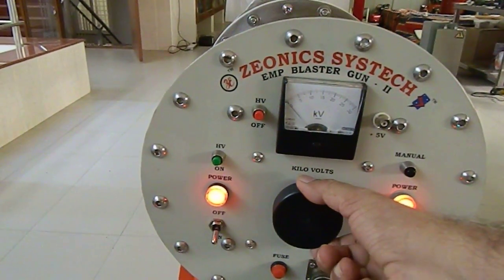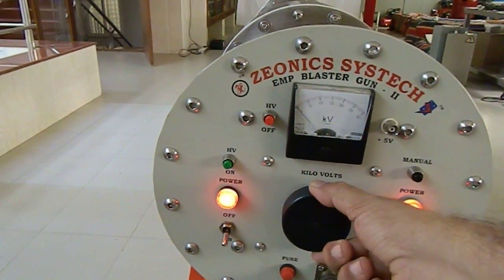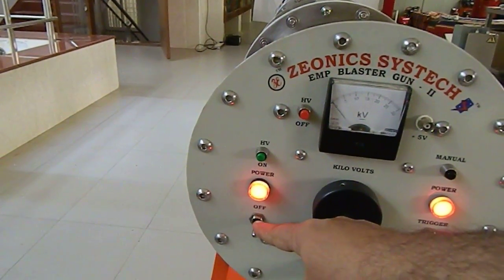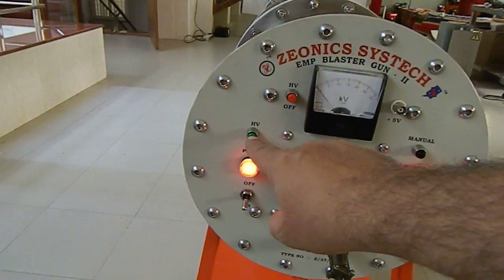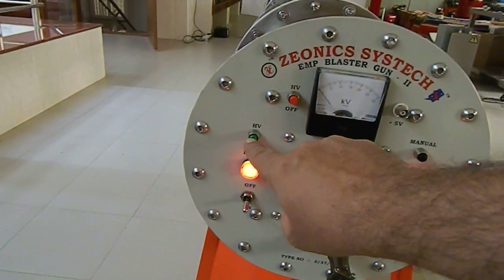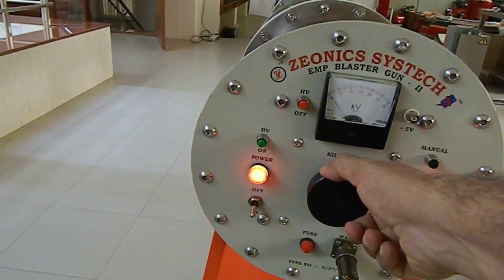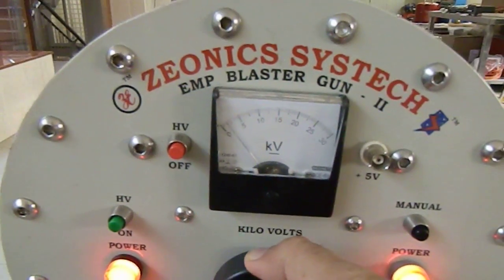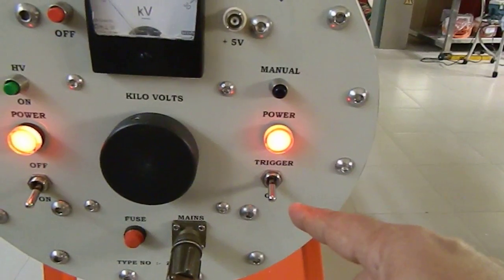This is the high voltage on-off switch. This is the power on-off. Once high voltage is switched on, then one can slowly vary the voltage and we can see the voltage will go up. This is the trigger mechanism which is optional. Best results are obtained while directly firing the system without trigger.